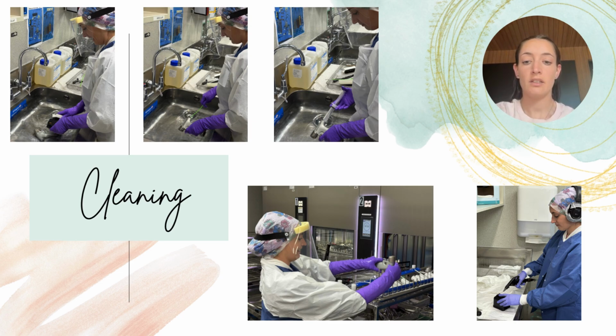Then I clean the reamer. So I put it into the sink. With the brush, I remove any visible blood or body fluids. Then with a long toothbrush, I clean it inside the cannula. I grab a syringe and flush it 3 times inside the cannula after that. Once it's done, I place the reamer on top of the cannulated washer rack to allow the reamer to be washed correctly outside and inside the cannula.